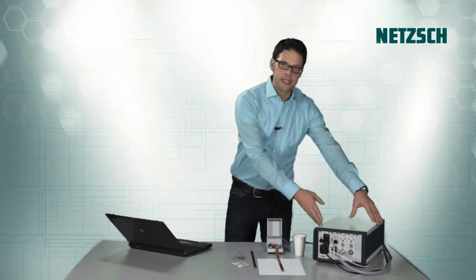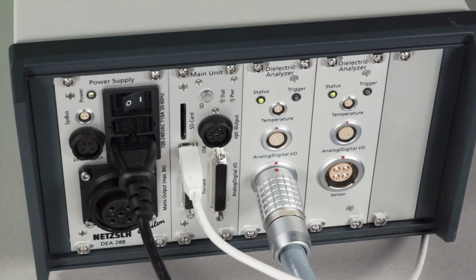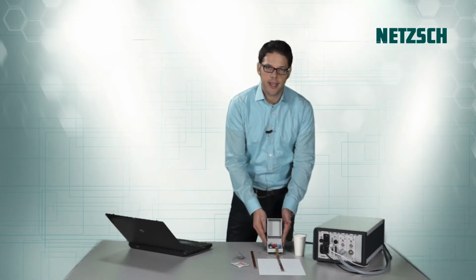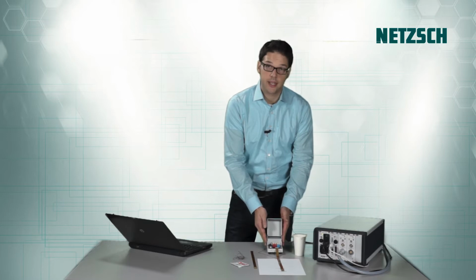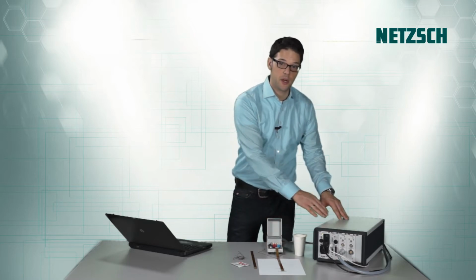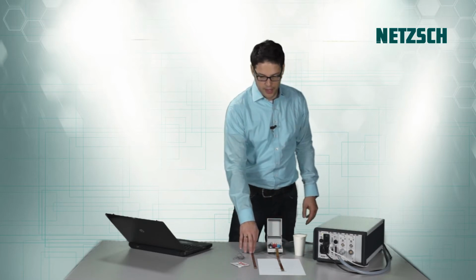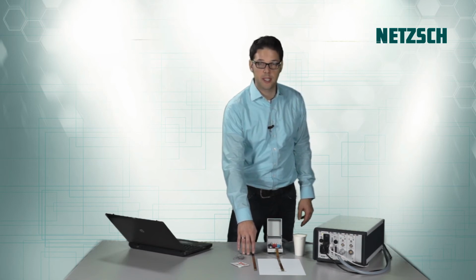Today, I would like to show you how to perform a simple measurement using the DEA 288 Epsilon Slimline. This is the instrument shown here with two channels. Additionally, we need an adapter box to connect a sensor to the measurement device. Here we have sensors, which will be explained later. And we need a computer, a standard Windows computer, to record the measurement.